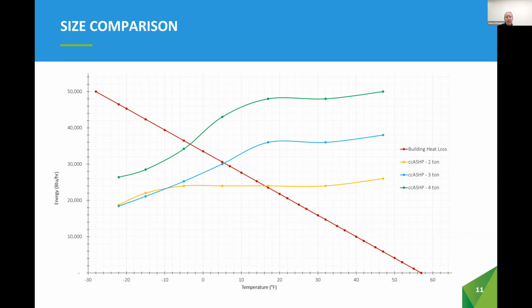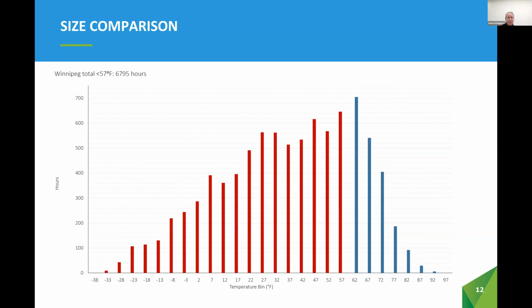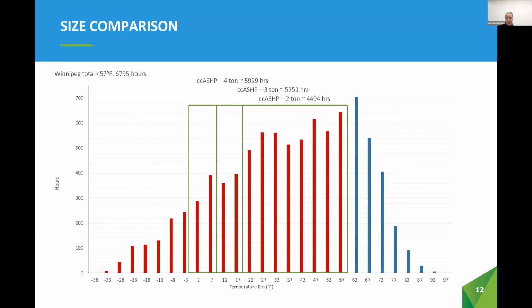This results in a balance point of minus 9 degrees Celsius for the 2-ton unit, minus 15 for the 3-ton unit, and minus 20 for the 4-ton unit. So looking at the hourly profile, we see that while the 2-ton unit falls outside of the recommended 70 to 105% sizing recommendation, it would still meet a significant number of heating hours in Winnipeg. Nearly 4,500 hours, which is 66% of our heating season. The 3-ton unit would meet about 5,200 hours, and the 4-ton unit is at about 6,000.